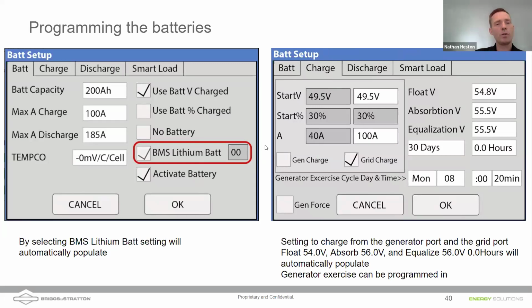If you're using our communicating batteries, make sure to check this box, the BMS lithium battery box. That will tell the inverter to look for that CAN bus communications coming from the batteries. You can also manually program these settings. If you check this box, the settings should be auto-programmed for you for charge and discharge, etc. These are global settings. So if you set that battery capacity and a max amperage charge, that means from any source, whether it's from solar or from grid, etc. And this max amperage discharge is a global limit, right? So that's the maximum that will allow those batteries to discharge.